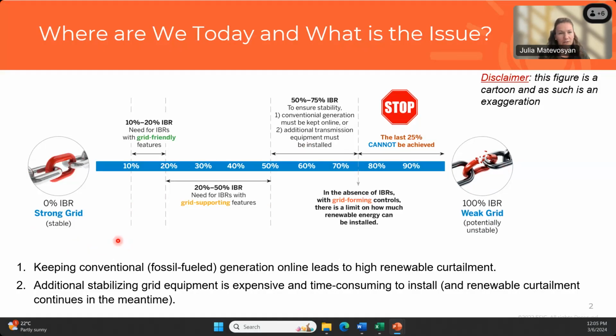On the right-hand side, we're at the other extreme at 100% IBR, a weak grid that can have potential instability issues. As we get to maybe 10 to 20% IBR—as discussed in the last panel—we can no longer let them trip offline during faults, so they need fault ride-through capabilities. We start requiring this from IBRs at this early stage of penetration. As we get to higher levels of IBR, not only do they need to stay online during faults, but they also need to provide supporting functionalities for the grid, such as frequency support, voltage support, and other ancillary services.